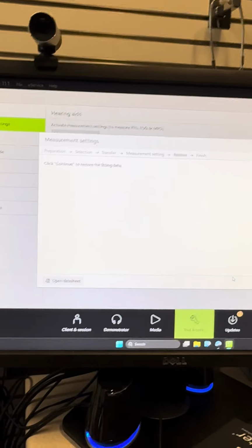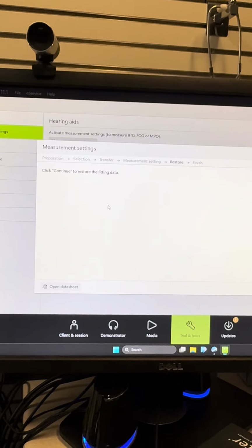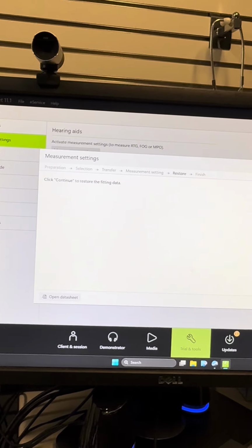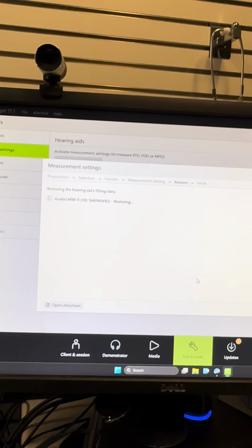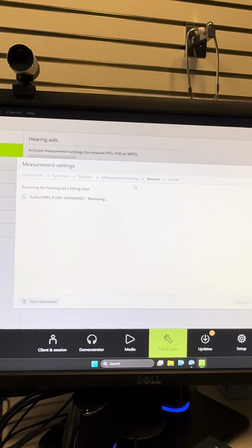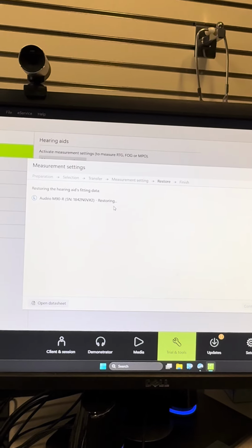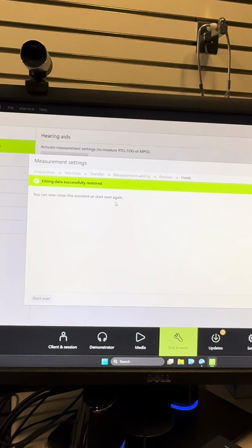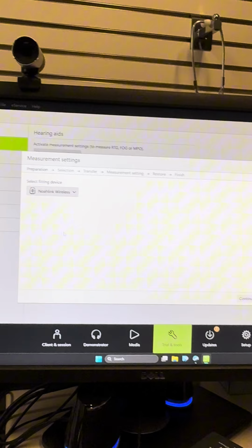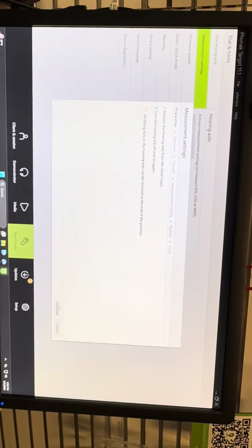Okay, now it's prompting us to set the hearing aid in reference test gain. Phonak's a little annoying in the sense where we have to turn the hearing aid off and on again to put it in reference test mode. Kind of go through this whole process. So it will restore the other hearing aid back to its original settings, and then click start over. Still using the Noah Link wireless. And yep, it's removed from the client's ears and it's trying to detect. We have to turn it off and on.